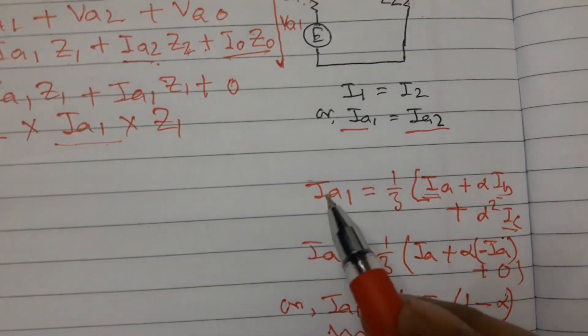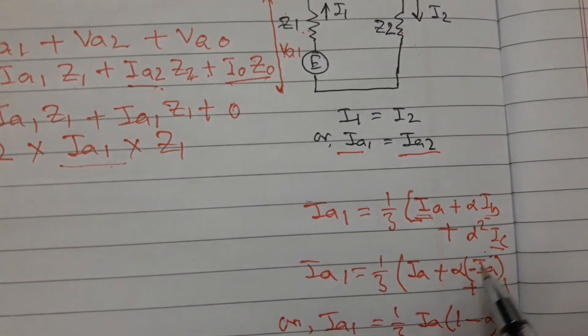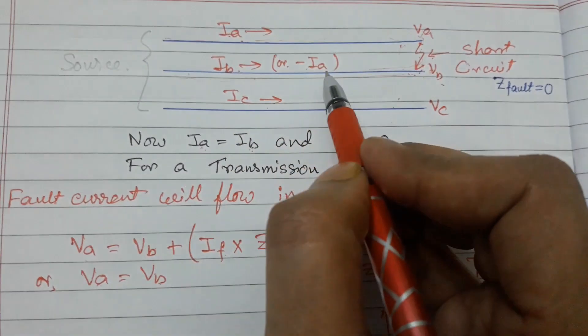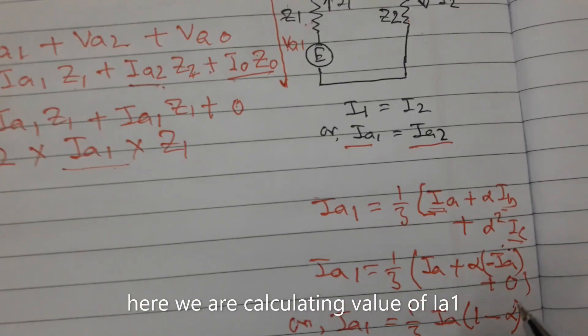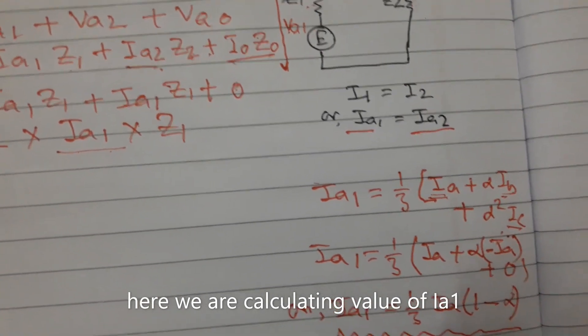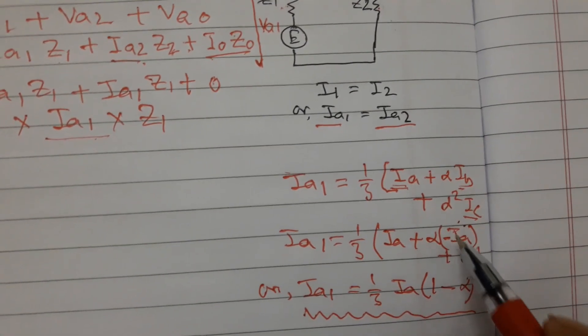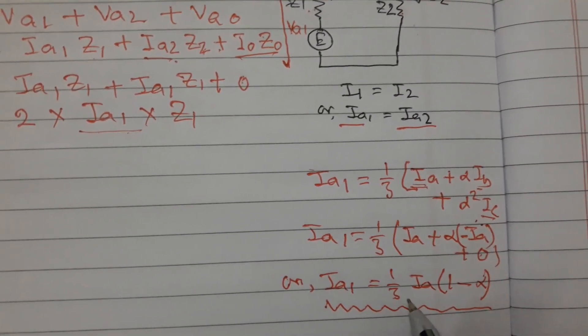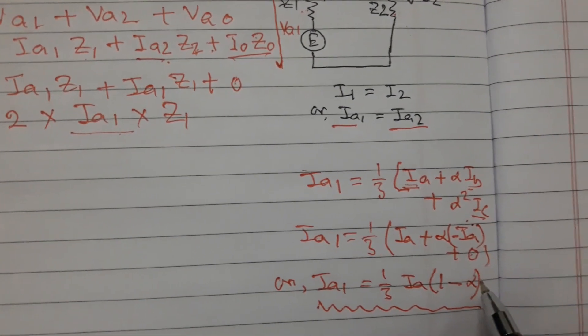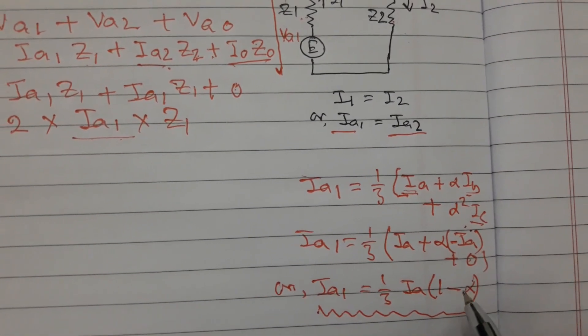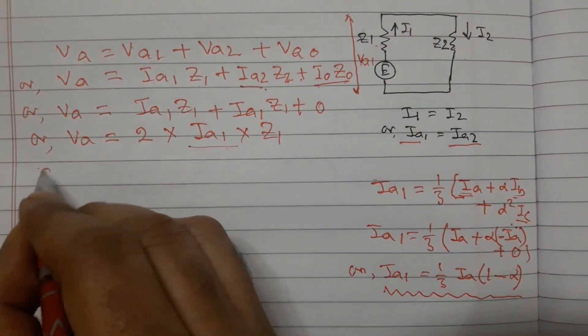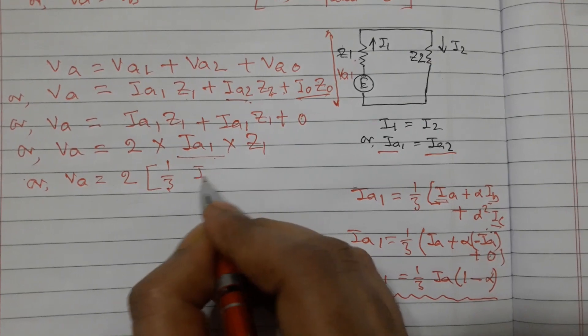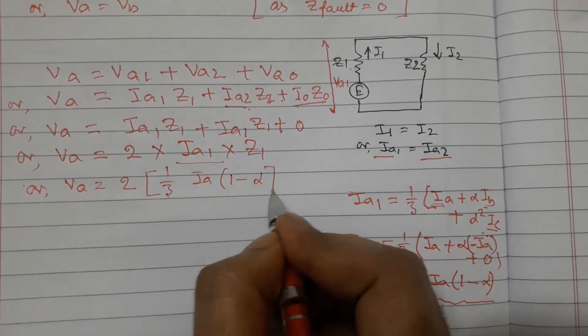We can write Ia1 using the sequence network formula. In this case, since the two currents Ia and Ib are equal in magnitude but opposite in direction, Ib equals minus Ia, and Ic equals zero. So we can write Ia1 equals one-third of Ia times (1 minus alpha), where alpha is the alpha operator of the sequence network. Therefore Va equals 2 times (1/3)·Ia·(1 minus alpha)·Z1.